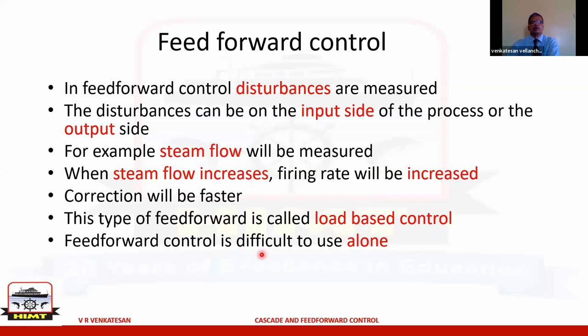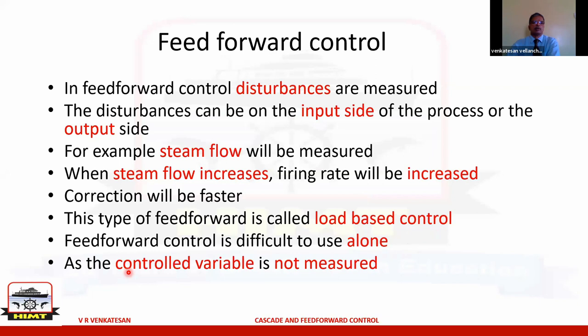Feed forward control is difficult to use alone — without feedback — because the actual controlled variable is not measured. For boiler combustion, the controlled variable is steam pressure. In feed forward, what you are measuring is the steam flow. Without measuring the steam pressure, it is not possible to control exactly. So feed forward alone is insufficient; it needs to be combined with feedback.